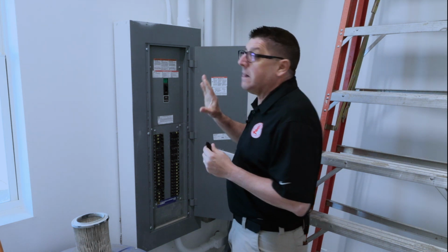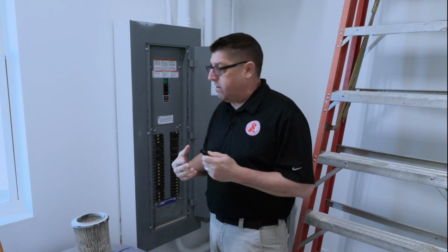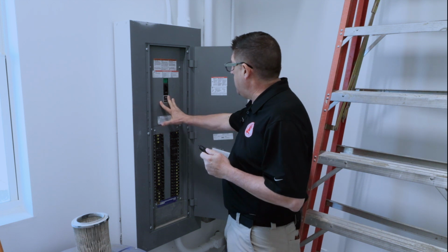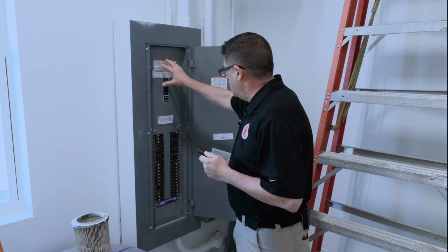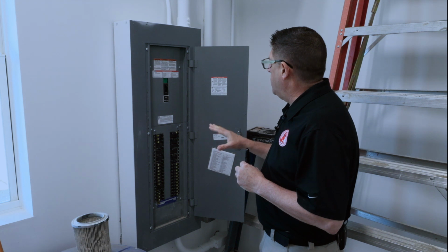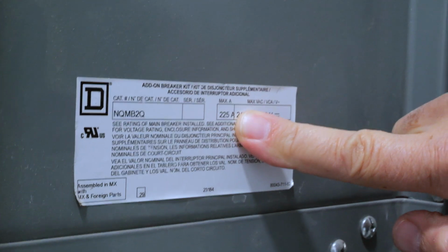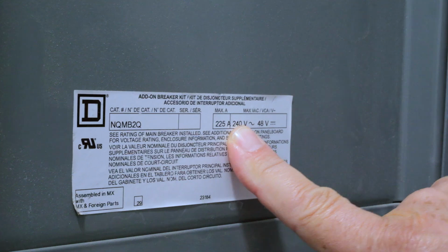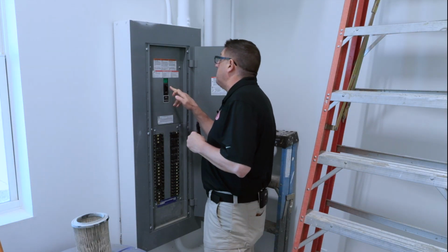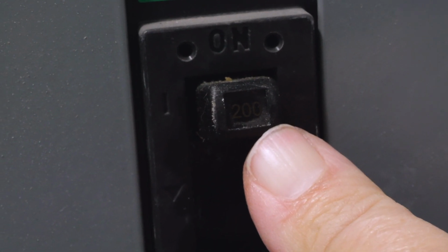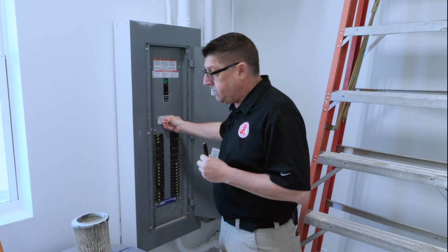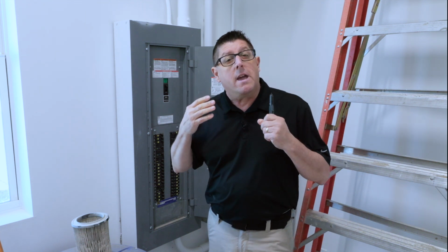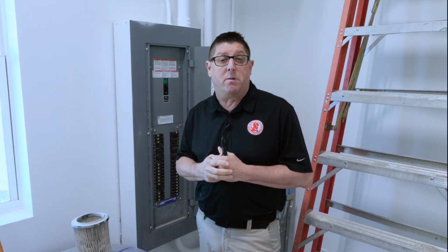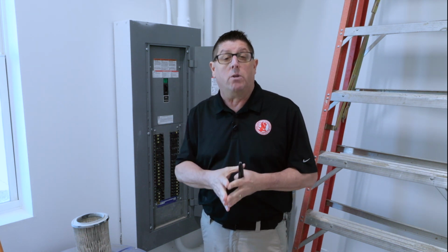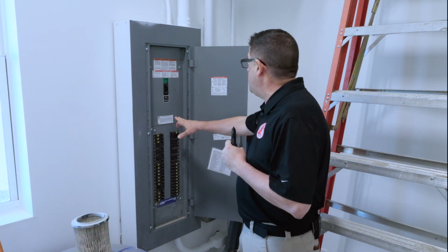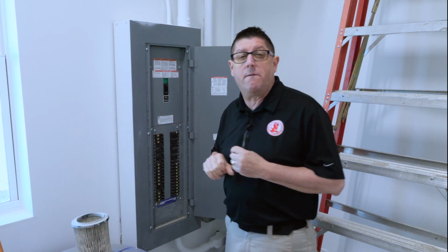So once again, like we've done in every other panel, I'm going to identify the main on this disconnect, as well as what distributes through. In this particular case, I'm looking at 225 for the panel rating. And so then I want to take a look at the main breaker, which is 200. Again, this matches this. But what's interesting, the electricity on the exterior of this building was 600 volts. But the panel on the interior is 240 volts.